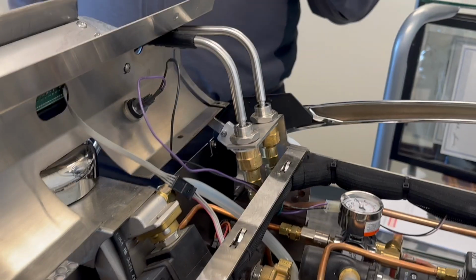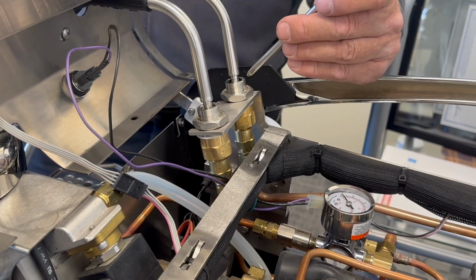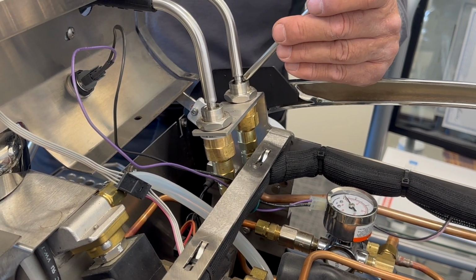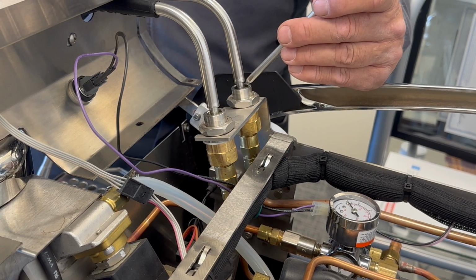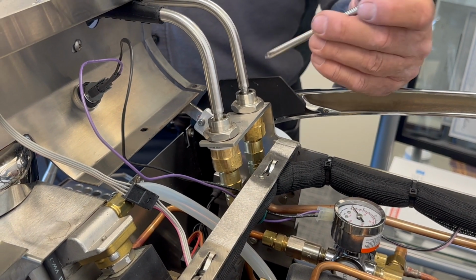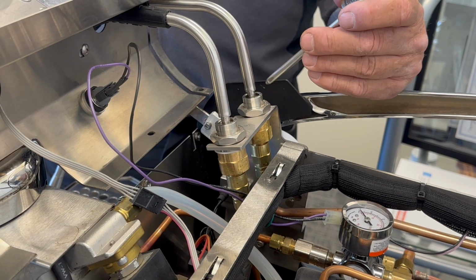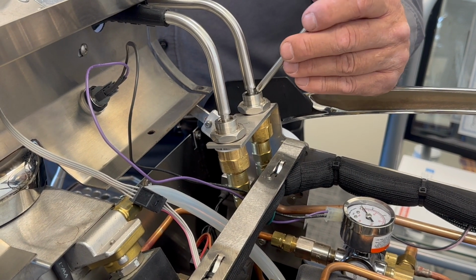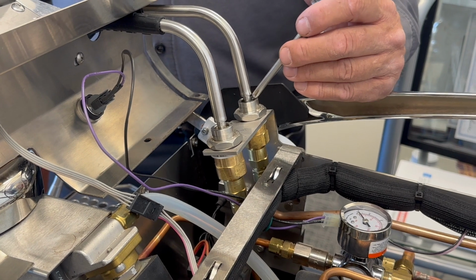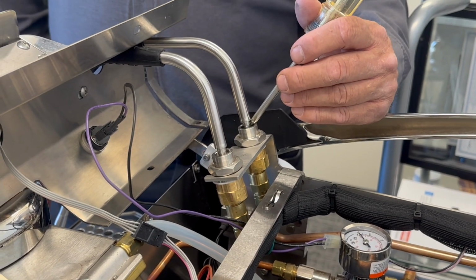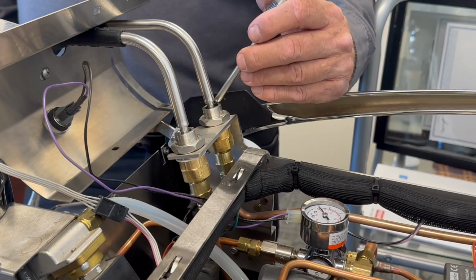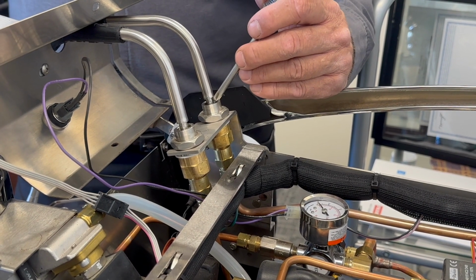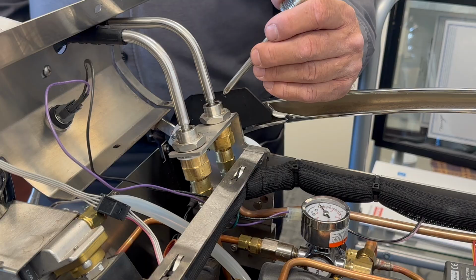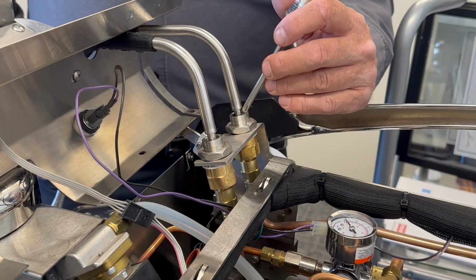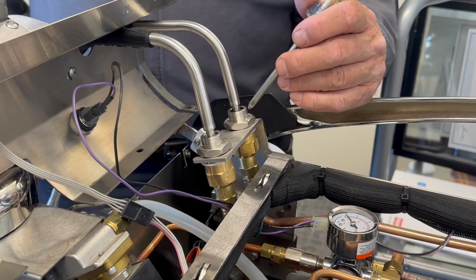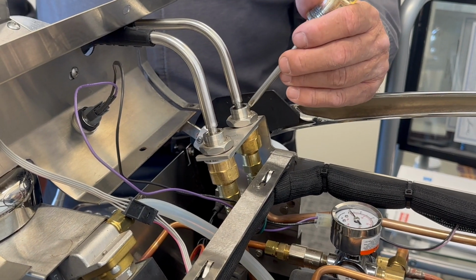I'd have to look at the materials, it's been a while since I've seen one of these apart, but if it's just Teflon in between everything, no. Anytime the ball is touching metal, that part needs to be lubed. So if it's metal on metal, or metal on brass, or this ball joint on brass, that part needs to be lubed. The ball joint itself will never wear because it's stainless steel, but obviously the other components can.